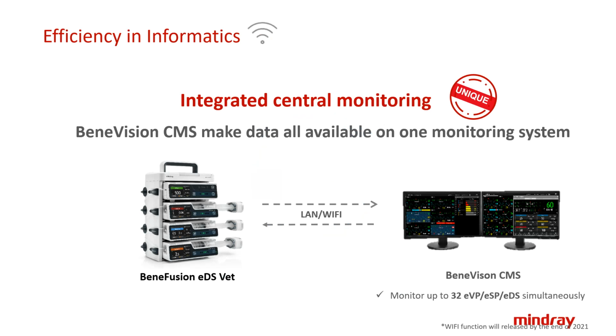Our BeneVision CMS can connect to the Benefusion EDS by LAN or Wi-Fi. Please note that the Wi-Fi function is not released yet on the EDS, it will be released by the end of this year. However, on the infusion pump or syringe pump, Wi-Fi is already supported individually. So if you plug the infusion pump or syringe pump into the docking station, you can only use LAN for now, and Wi-Fi support on the docking station will come by the end of the year.